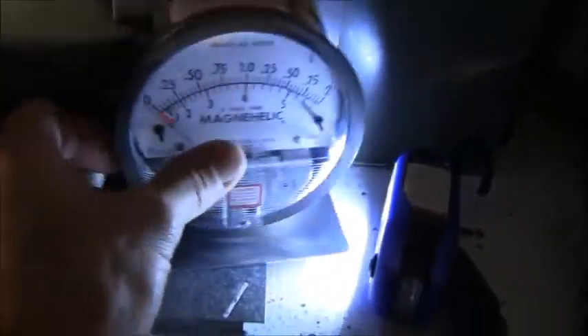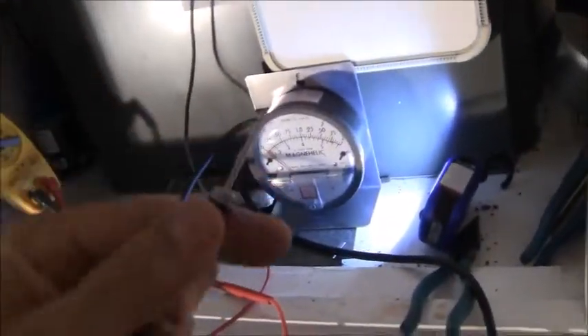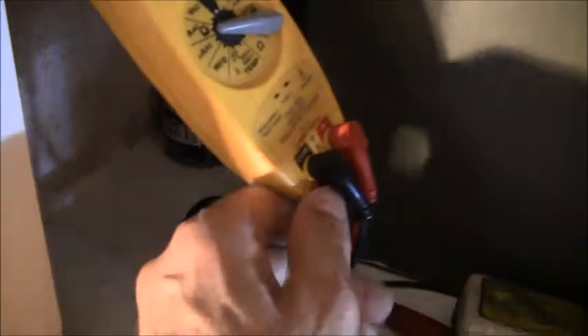Now remember, when you're looking at the Magnehelic gauge, there are 2 readings, the high and the low. The high is on the top, the low is on the bottom. This one here you can see is the high, and the one underneath is the low. Because my expectation is that this is below atmospheric pressure, I want the low, the bottom tap. I actually have 2 needles, so let me switch this around. Okay, here is my low pressure port. Make sure your hoses are not kinked at all. Then I'm going to put this down into here, which is supposed to be getting the pressure below the pre-filter, and I'm going to see if the gauge reading moves.